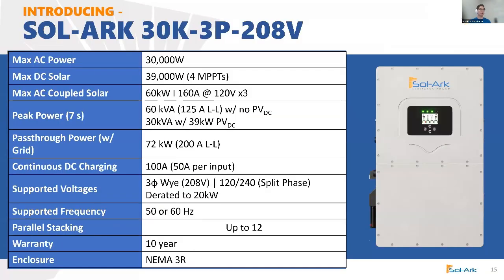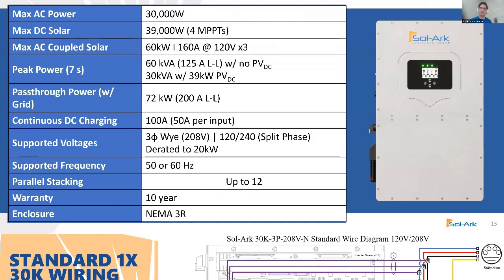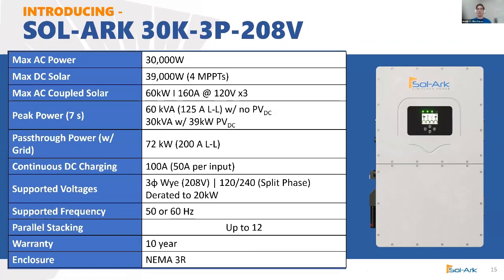And for the 30K itself, we're going to go ahead and just talk a little bit more about that. It's going to be a nameplate of 30,000 watts that you can output as AC. You can input 39,000 watts into the 4 MPPTs on the Sol-Ark, and they are used with the push actuation levers, so it's extremely easy. Just ensure that those cables have about 5/8 of an inch stripped, and then you're able to just go ahead and insert. It's that easy. You can AC couple as well simultaneously, 160 amps at 120 volts. And the peak power, depending on whether you have PV, it's going to be about 60 kilovolt amps or 30 kilovolt amps with the maximum amount of PV DC.